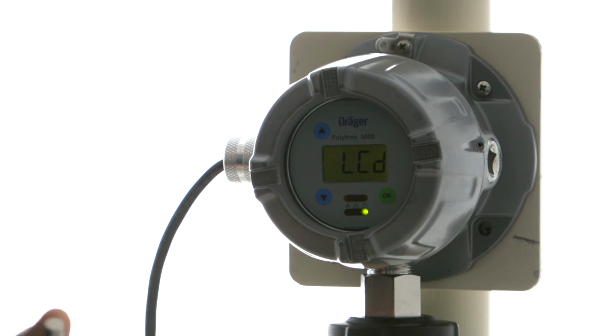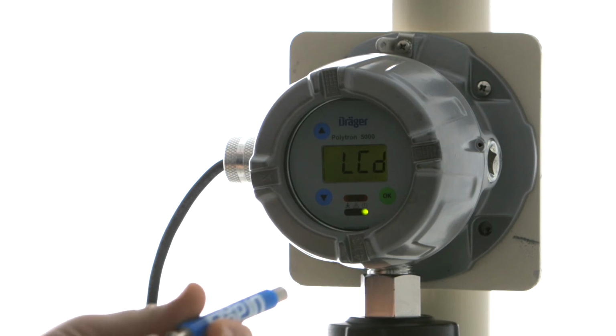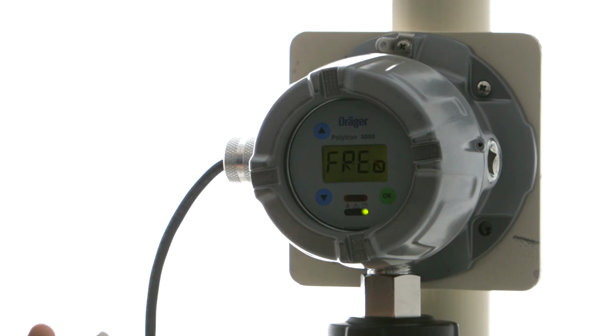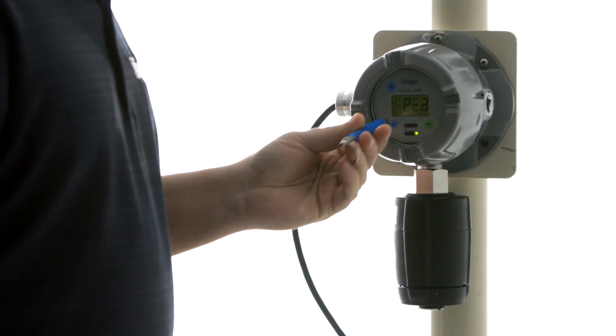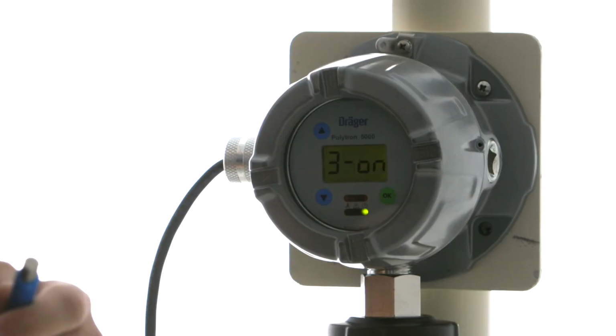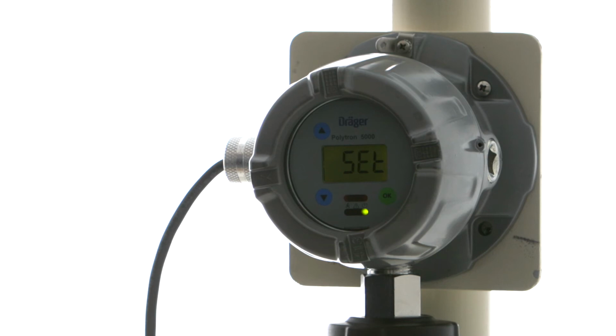When we move on to the LCD screen turning on and off, that's exactly that. We can turn the LCD screen off if we like. By default, it's on. And again, the failure or fault signal below 4 milliamps, that could be set as well with this menu item. And you can also set the Polytron 5100 for 2 or 3 wire mode. By default, the Polytron 5100 is in 3 wire mode, but you can set it to 2 wire mode if need be. Once you set it, you will need to power cycle, and then the unit will be in 2 wire mode.